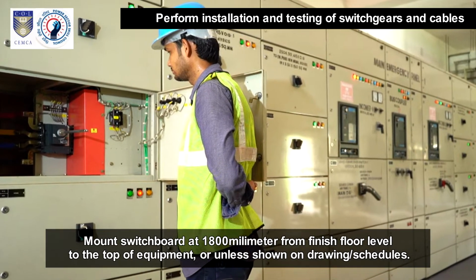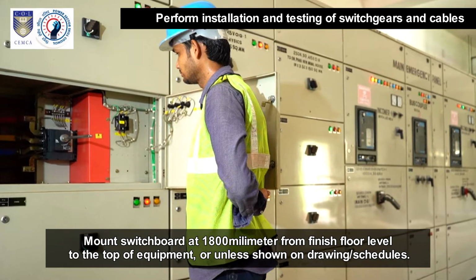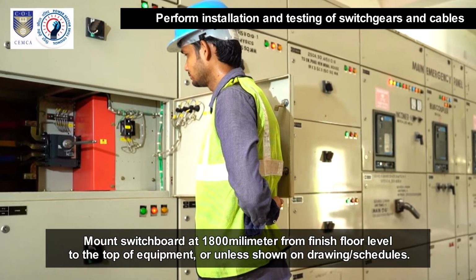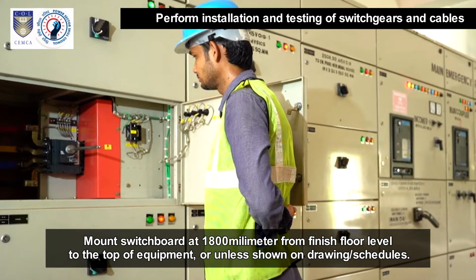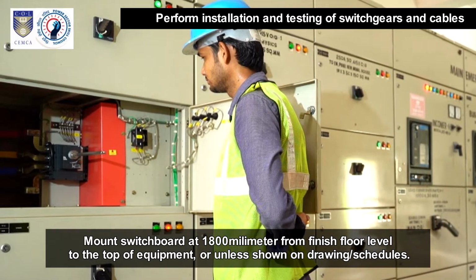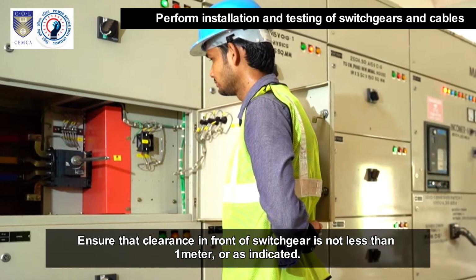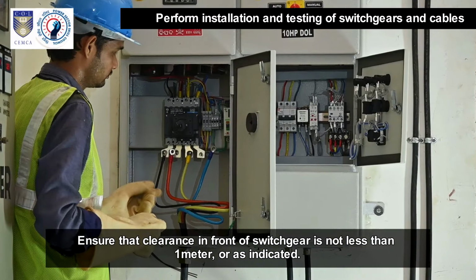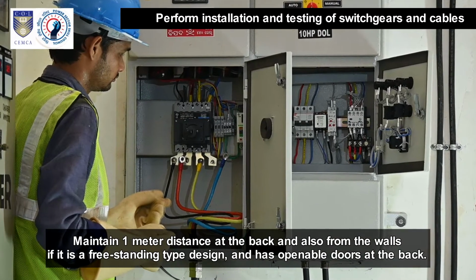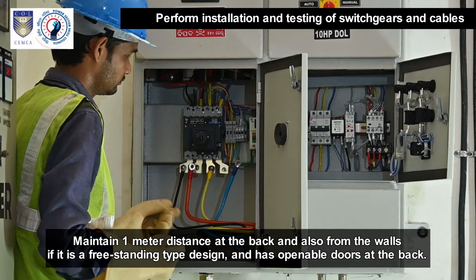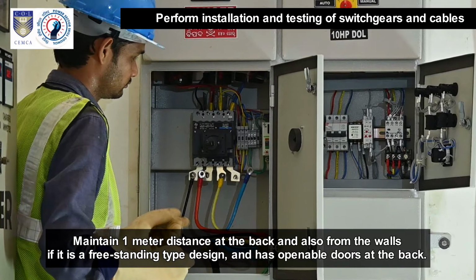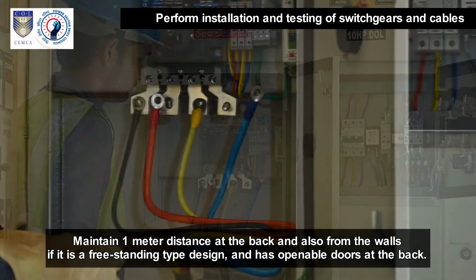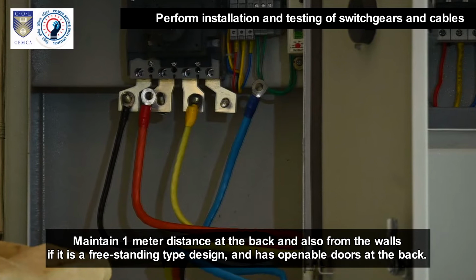Mount switchboard at 1800 mm from finished floor level to the top of equipment or unless shown on drawing or schedules. Ensure that clearance in front of switchgear is not less than 1 meter or as indicated. Maintain 1 meter distance at the back and also from the walls if it is a freestanding type design and has openable doors at the back.